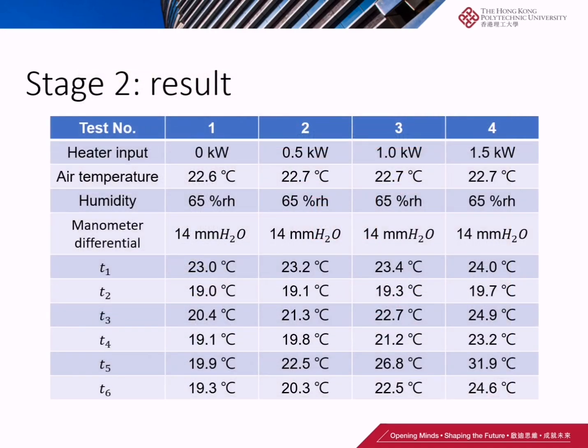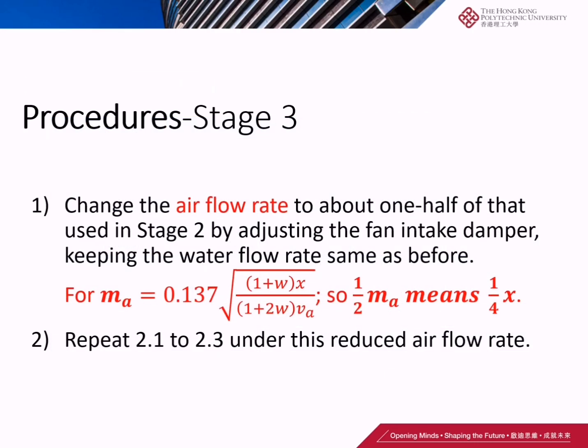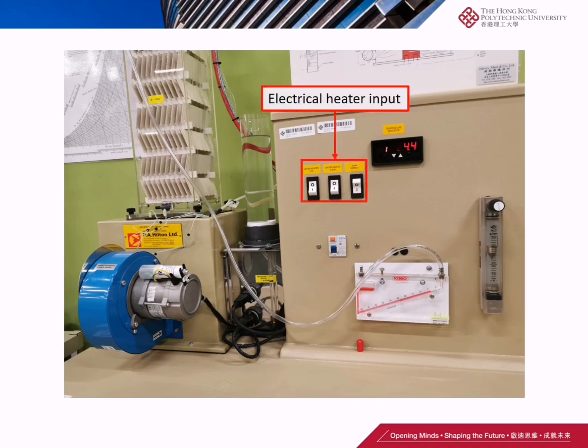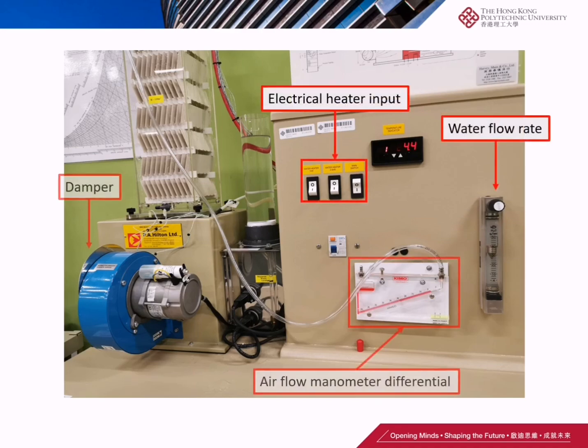Here is the table of results in 4 steps. For Stage 3, we need to change the air flow rate to about one half. According to the formula, we need to adjust the differential to one quarter of the baseline value by adjusting the fan intake damper, and keep the water flow rate the same as before. Then repeat steps 2.1 to 2.3 to reduce the air flow rate. You can pay attention to the change of the damper.